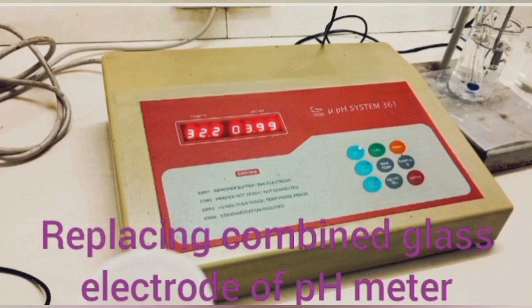Now today we will tell you how we replace the combined glass electrode of our pH meter. Actually, if the pH meter is in good condition and you have changed the internal saturated KCl solution, even though this is not working, try to change the pH 4.0, 7.0, 9.2 buffer solutions, and then see whether the machine is working or not.